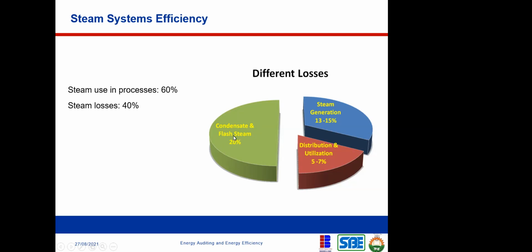I've explained to you what condensate is, right? Then flash steam, I think is in the next slide, I'm going to explain what the flash steam is and all of that. But essentially, there are leakages, right? Maybe you have holes in your piping system where through these steams can leak through and stuff like that. So when you have those kind of things, you have a flash steam leaving the system from those kind of holes. Then you have steam generation. At the point where you're generating the steam, you have losses of between 13 to 15%.